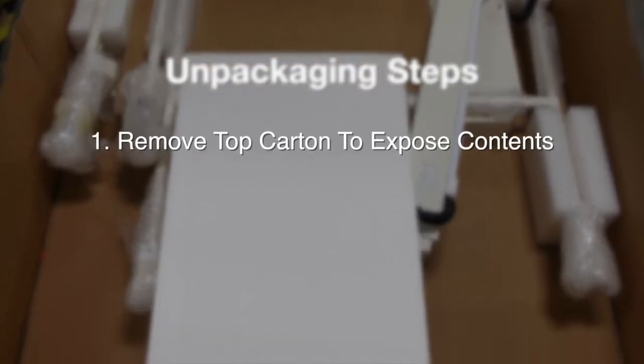The imaging device will arrive in secure packaging such as this. After you remove the top carton to expose the contents, you want to first remove the top polystyrene cushion, which secures the generator, and go ahead and set it aside. Next, cut off the 3 cable ties on the patient handrails. Carefully lift the arm of the podiatry support base up to 90 degrees, remove, and then gently set aside.